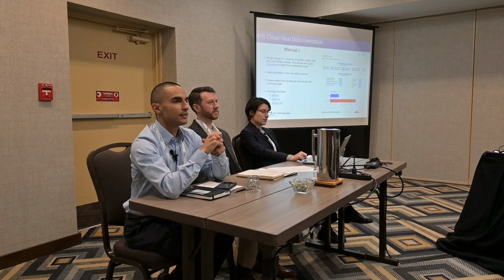Yep. Go ahead. You mentioned you Manual J, so you don't have comfort issues yet. When you size for heating load, a typical home in upstate New York might have a 2-ton air conditioning load but a 5-ton heating load. And when you size for the heating, you're going to have comfort issues, either with ductwork not sized properly or you're oversizing. What do you do in those instances?